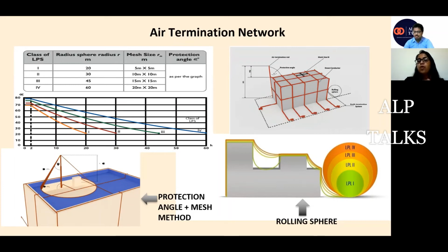The points where this imaginary sphere touches my building will be more vulnerable to lightning strikes. So I have to install the air terminals at those points. I have to put the air terminals in such a manner that the 60-meter sphere fits between my air terminals and does not touch my building or my roof. In that manner, we do the designing through rolling sphere.